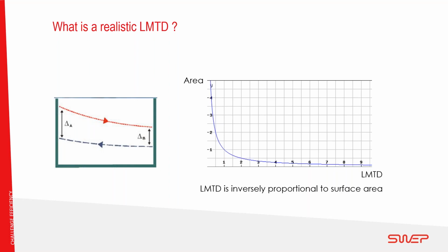As the LMTD is reduced, there's a diminishing return from additional surface area below a temperature difference of around 1 degree Celsius. This means that from a system design and capital cost perspective, it can be beneficial to keep the LMTD above 1, and SWEP may even advise in some cases to keep it above 3 if possible.